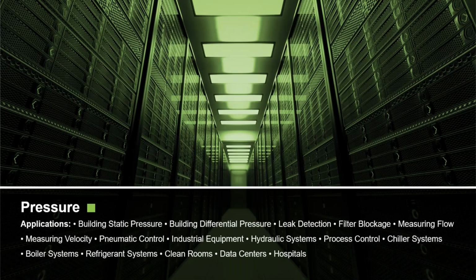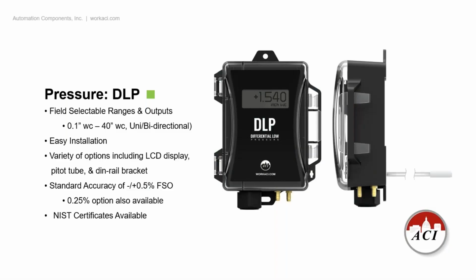We then started manufacturing pressure sensors probably 15 years ago. We get involved with both dry and wet applications. The DLP here is our bread and butter for dry differential pressure transmitter applications. What customers like about this is it is a 0.1 to 40 inch jumper selectable range, everything in one device. So we have the high and low barb fittings, and we also have a duct pitot tube and a DIN rail all on the enclosure. We own this enclosure. It's completely screwless. You do not need any tools at all to get into this device. Press fit enclosure side tab, optional display.